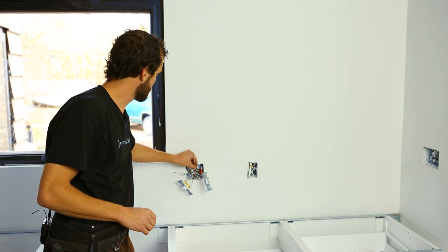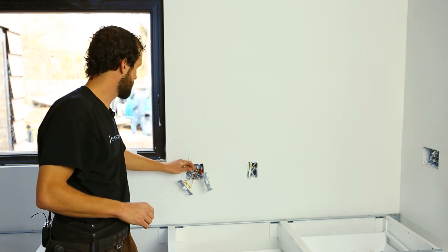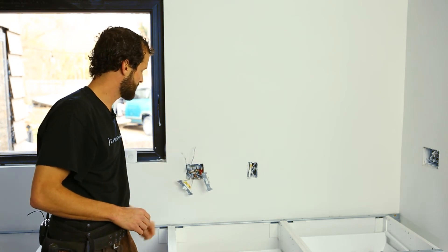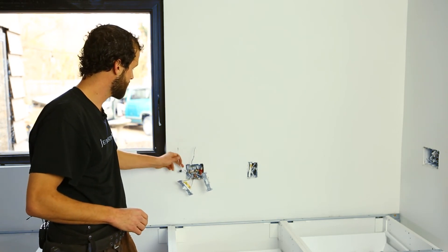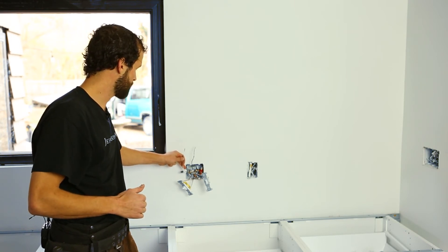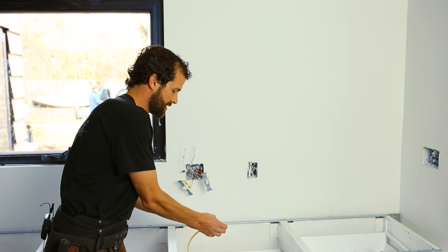And now this is where I've got two wires and two terminals. You might think it's cut and dry, real clean. But in fact, I need both of these to be energized as hots. And I need both terminals to be energized as hots. And right now, all I have is one hot conductor. When that breaker goes live, this is the only thing that will be energized. So I'm going to use the pigtailing method.